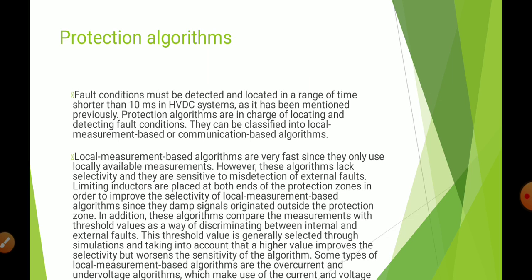Limiting inductors are placed at both ends of the protection zones in order to improve the selectivity of local measurement based algorithms since they damp signals originated outside the protection zone. In addition, these algorithms compare the measurements with threshold values. What are threshold values? We give a threshold value, and values above or below it are taken into account as a way of discriminating between internal and external faults.